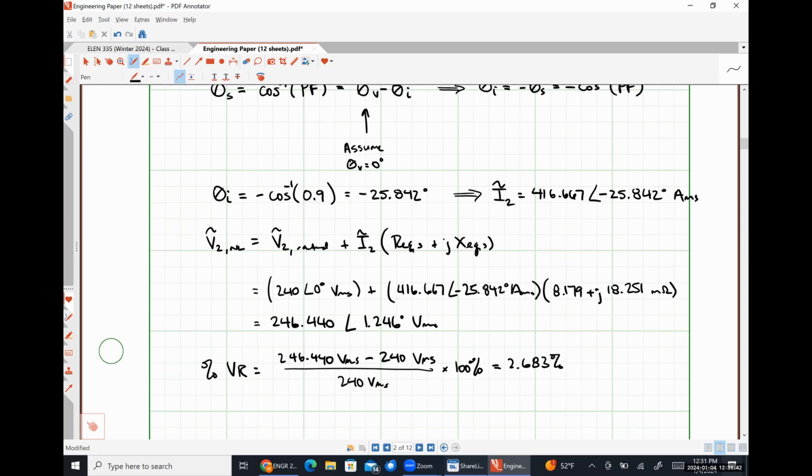like that. So for an arc welder, it takes a very, very high amount of voltage in order to establish your cutting beam. And then once it's established, it actually only requires a very small amount of voltage to maintain it. So a transformer in an arc welder is usually one that's designed for bad or poor voltage regulation, so that the voltage at the secondary drops down low so that you're not just wasting power converting it into heat, because you don't need that high voltage. Same thing for discharge lamps and all that kind of stuff. So there is a practical place for transformers with low voltage regulation. It just is not in power distribution.